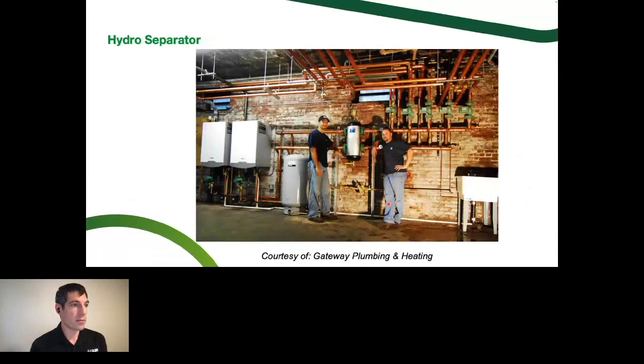Okay, here's a project example of a hydro separator. So what I would point out here is to get primary, secondary piping right with all the proper spacings, you can actually go right into a hydro separator with an elbow. There are no minimum distances here like with closely spaced tees. This is a pretty small amount of real estate for what might be 2-inch, 2.5-inch pipe with those two boilers combining. So that's a pretty big pipe. This, if it were closely spaced tees, might be wider than the shoulders of these two guys that did the installation that are having a good time showing off this cool job site. So that is a very small package to do primary, secondary correctly.